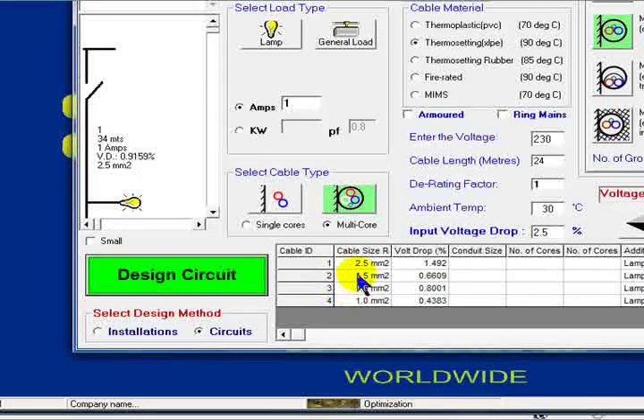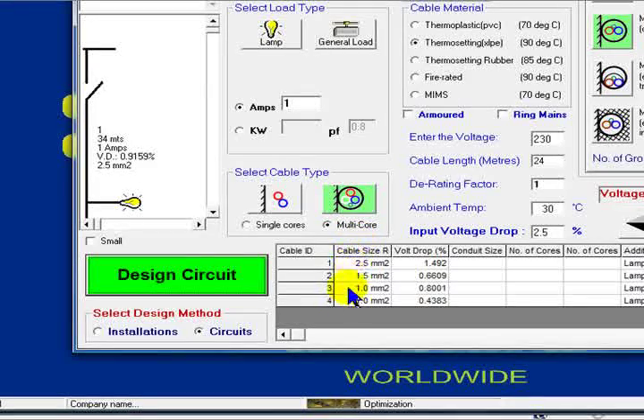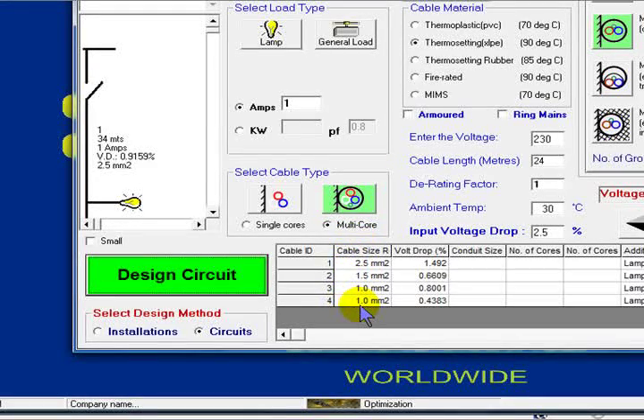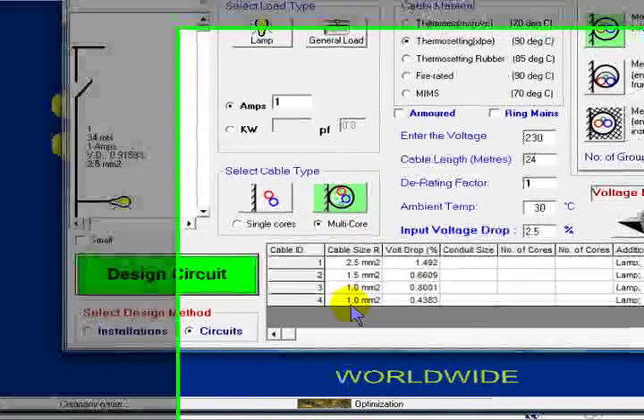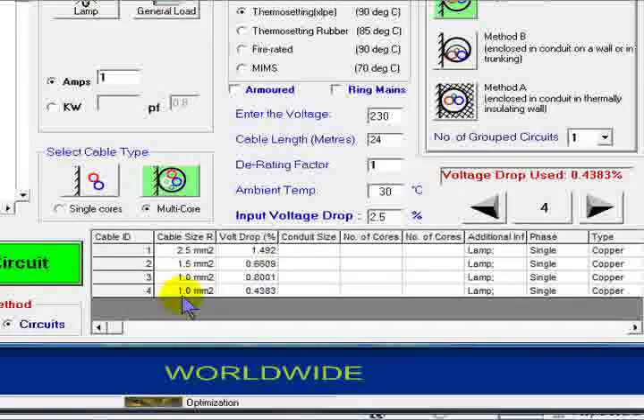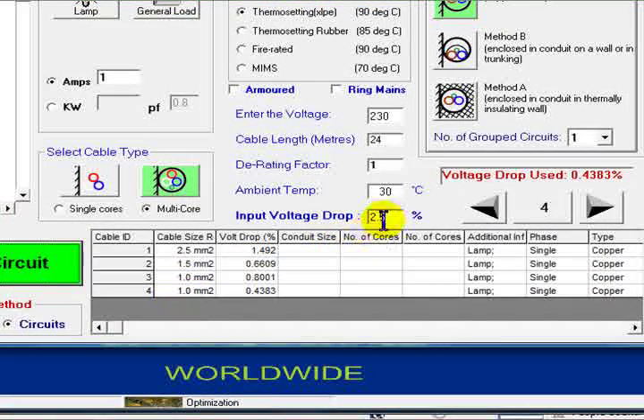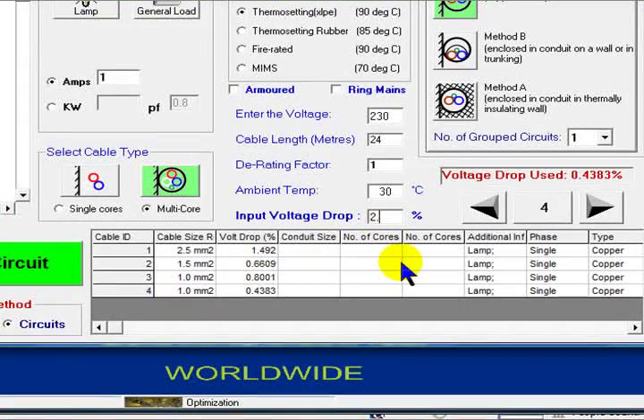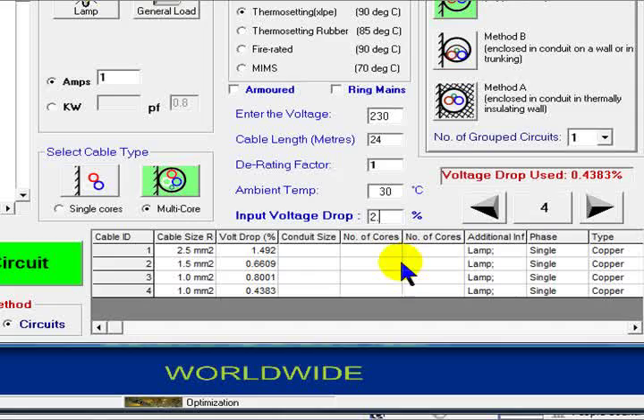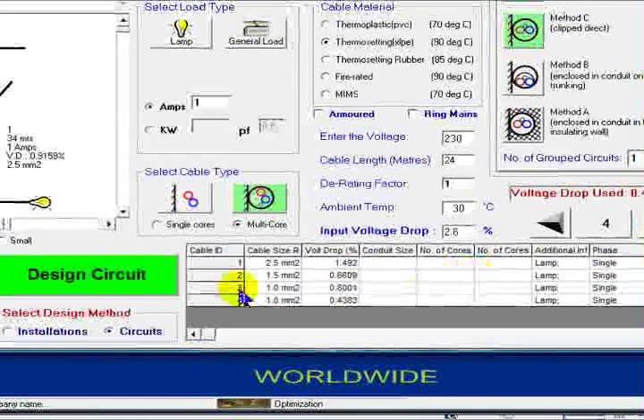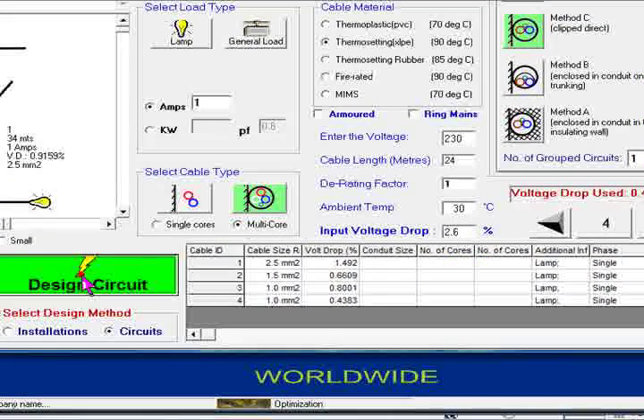The program has given us a 2.5, a 1.5, a 1mm and a 1mm. Now we can actually adjust our voltage drops. Hopefully we can get our cables fairly similar in size. So we'll take that to 2.6 and redesign the circuit.